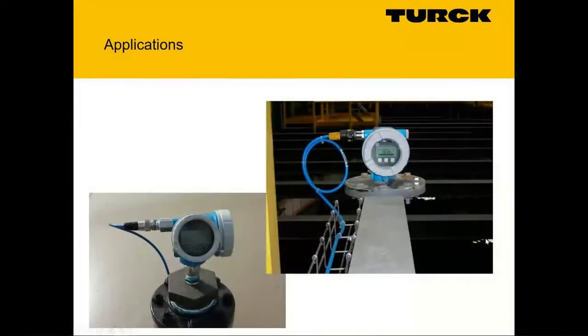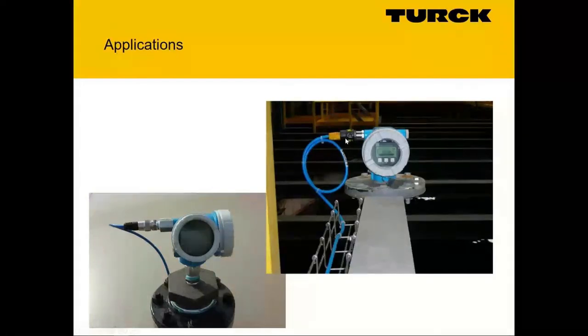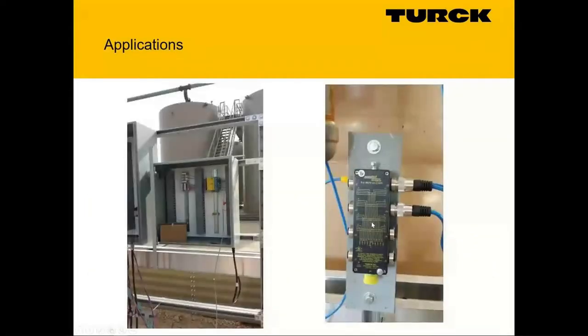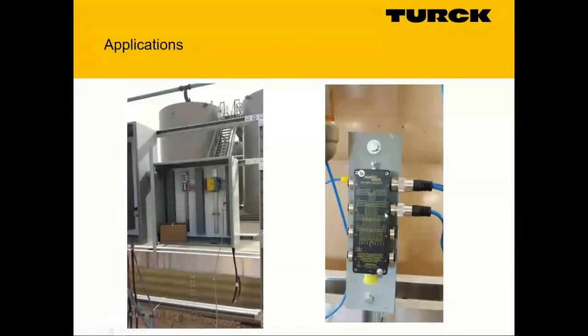A couple of intrinsic safety applications: our cables can be run in tray instead of conduit — with exposed-run cables we can clip them under beams as long as they're mechanically protected. Here's another Division 2 application outside the bunds, using barriers for intrinsic safety — this is Continental Resources, everything plug and play and they're in the process of wiring it up.